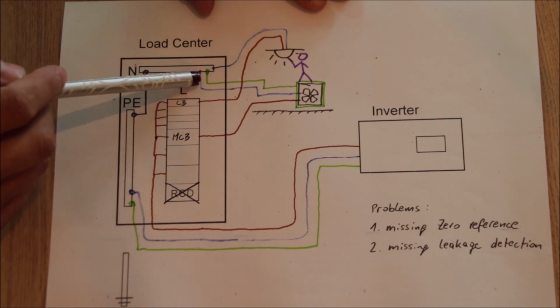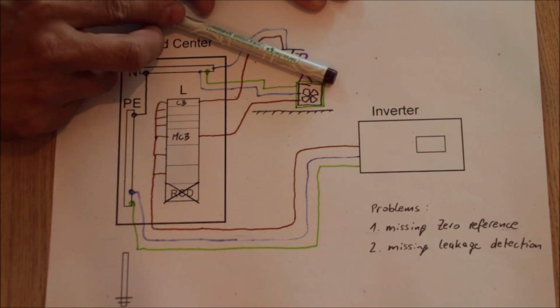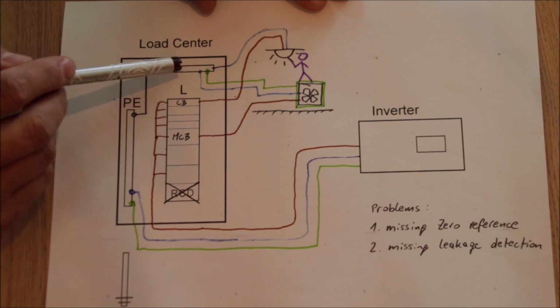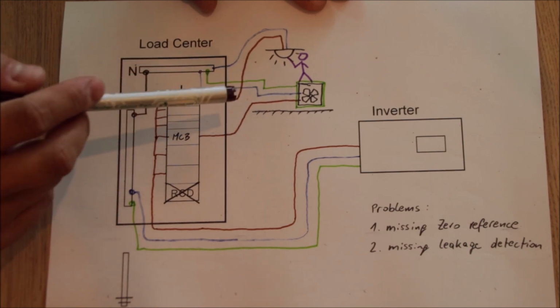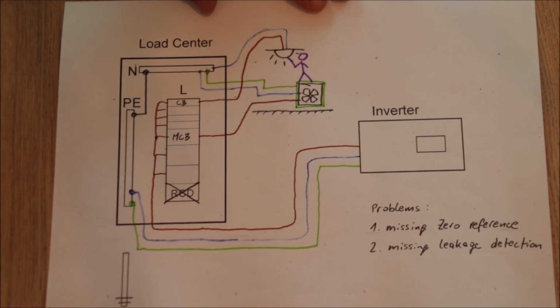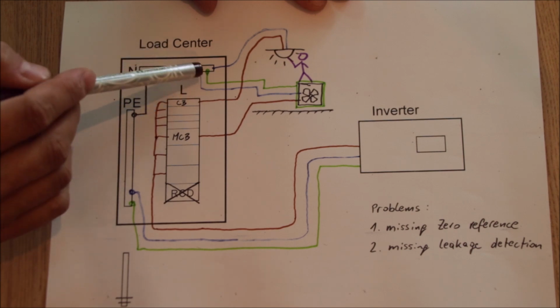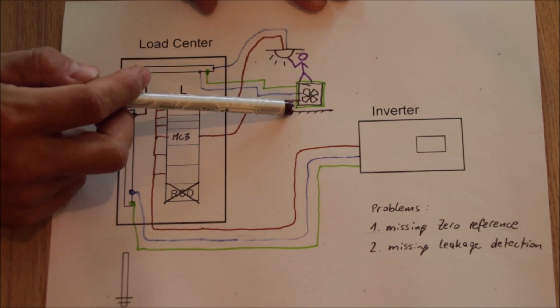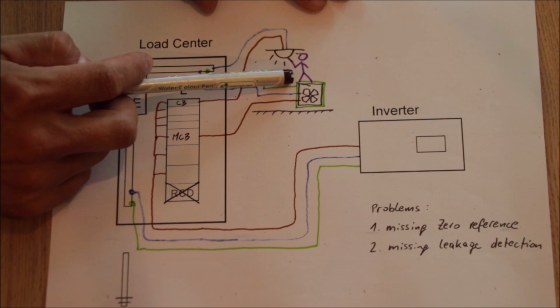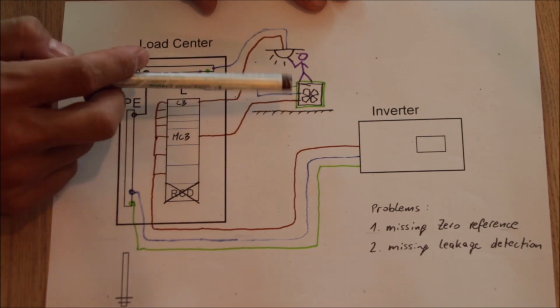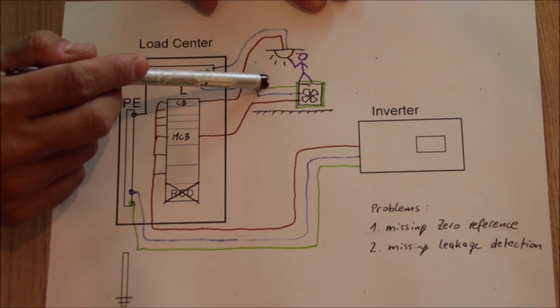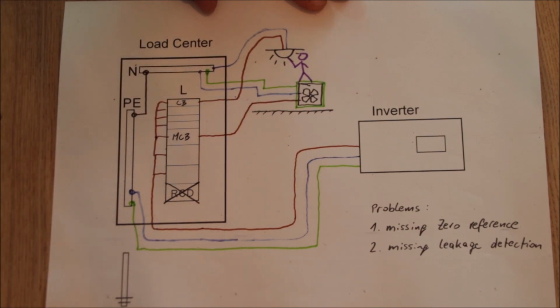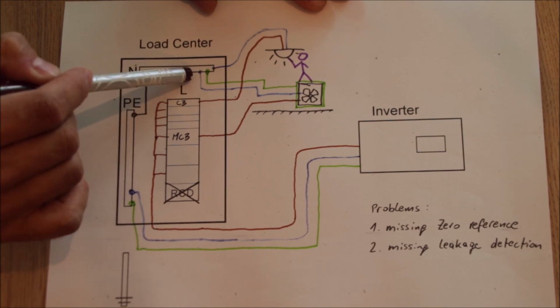Well, look at the air conditioning circuit now. So he connected L, N and PE, and PE and N again ended up right next to each other on the, in this case, neutral bars we have in all of the panel now. So what you have learned before is that the PE with the appliance, with a bigger device like an air conditioner compressor unit, which does have a metal casing, now becomes a part of active neutral, right? Because it is coming from the same source.